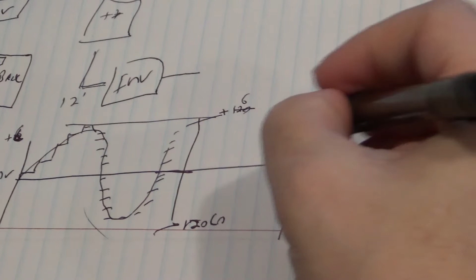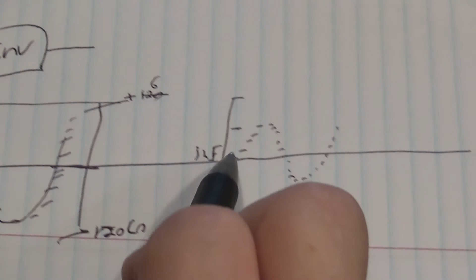So what happens when this length is too long is that when it does this step up and step down, it's starting with, let's say, 11.5 because of the voltage drop of your cable. It's starting here, not here. So it only can reach up a certain point. And because it can only reach up a certain point, with your step-up transformer, you're going to get a sine wave that doesn't reach properly, because of the voltage drop.